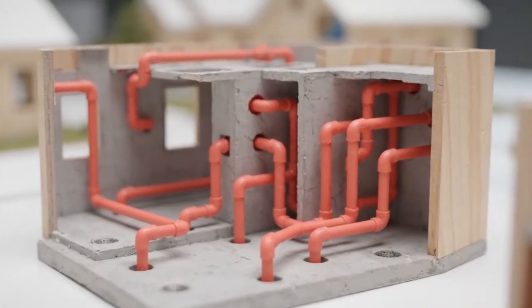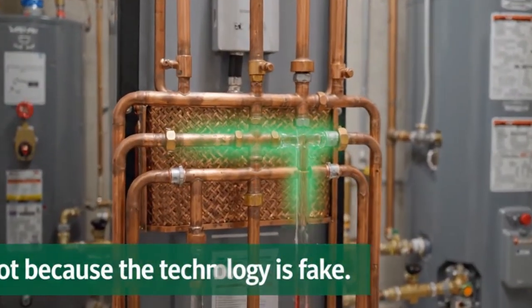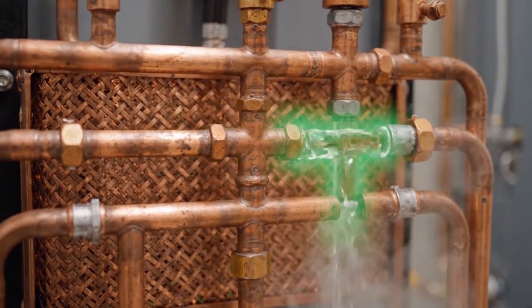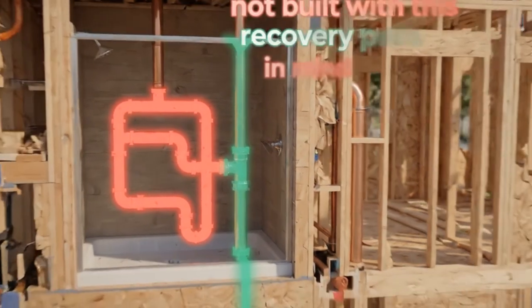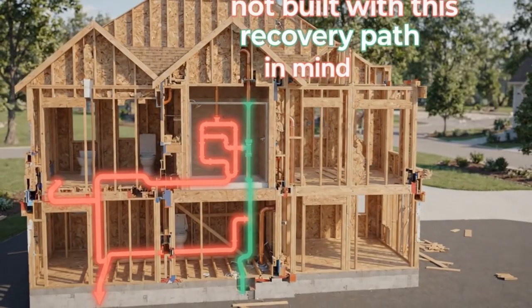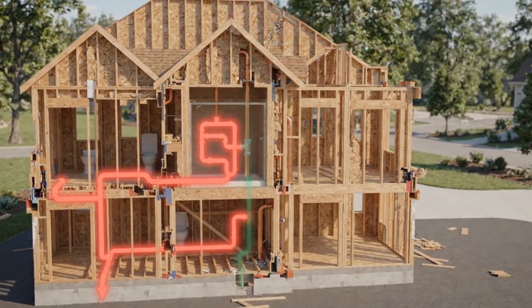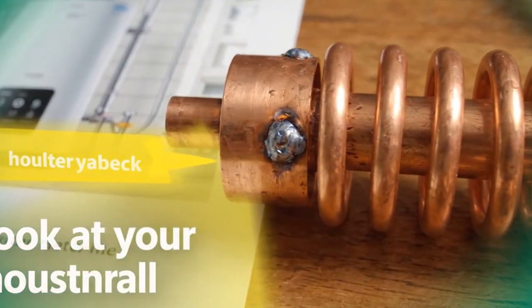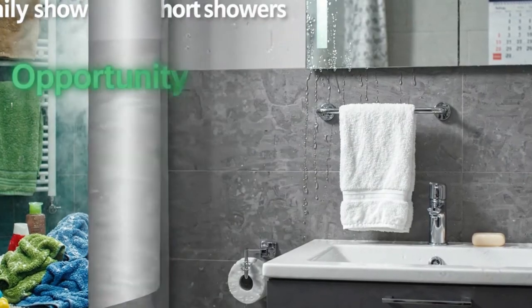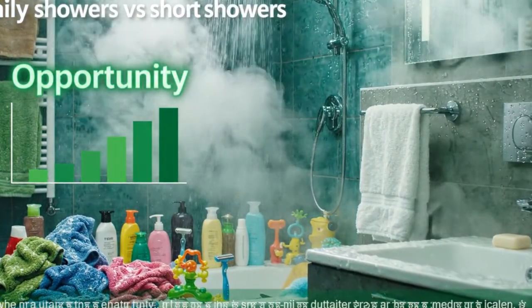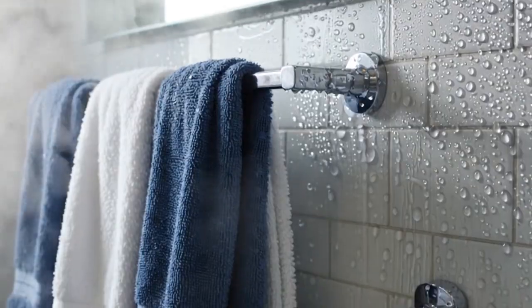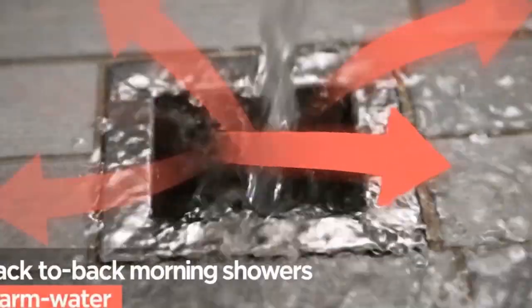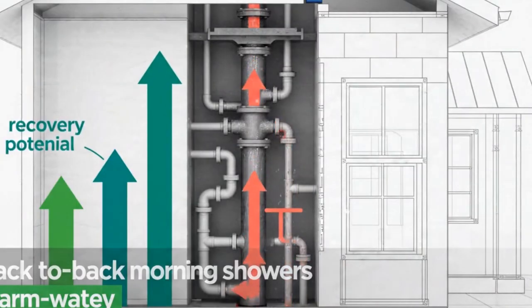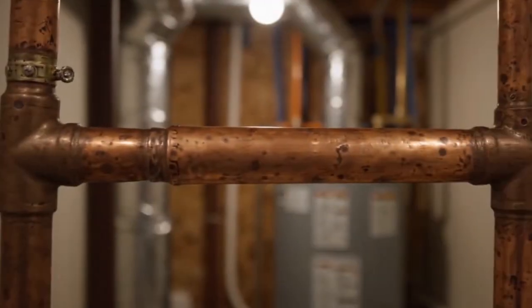Start with the shower, not the kitchen sink, not the washing machine, not the dishwasher, the shower, because a shower creates the cleanest opportunity. Warm water is falling down the drain at the same time cold water is being pulled into the plumbing system. That simultaneous flow is what a simple, non-storage drain water heat recovery unit needs. If the warm drain water is leaving while cold water is entering, the heat exchanger has something useful to do. If those two events do not overlap, the opportunity becomes much smaller.